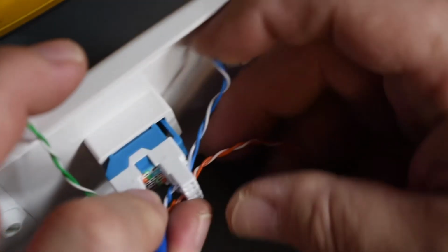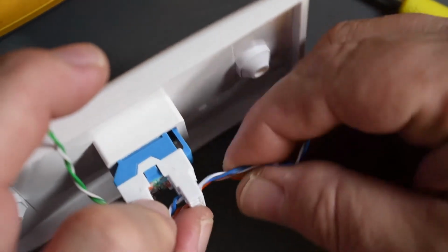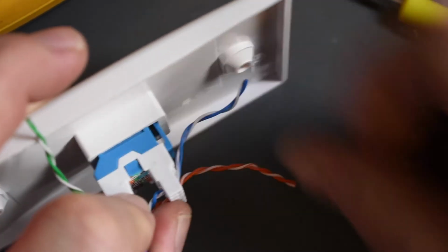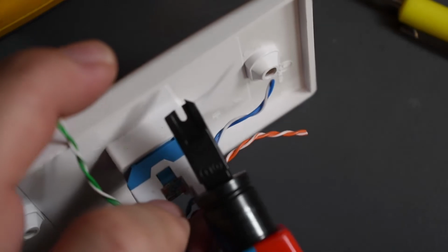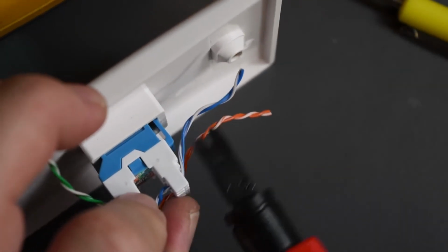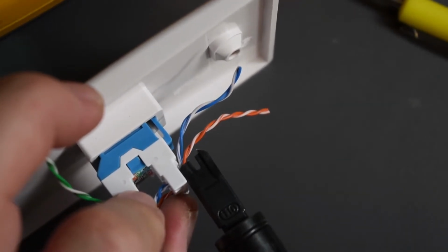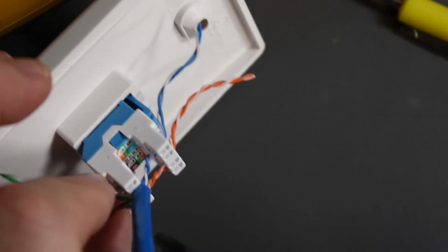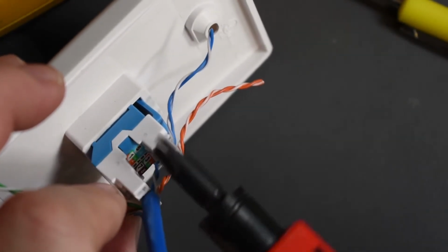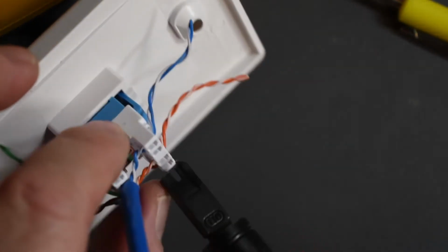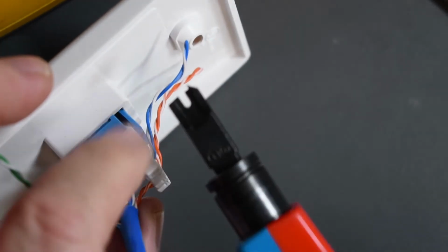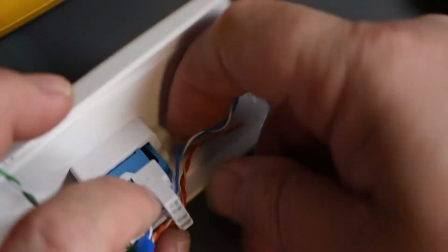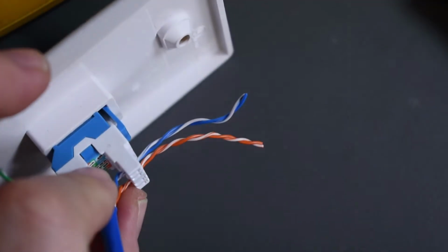So I'm just going to make sure that those wires are sitting straight, because when you punch down, the knife has to be pointing this way, so these wires are cut off as I punch them. If you put the knife that way, you're going to cut your whole cable off on this side. And if the wires are leaning against the wall, the knife is going to have a hard time reaching them.